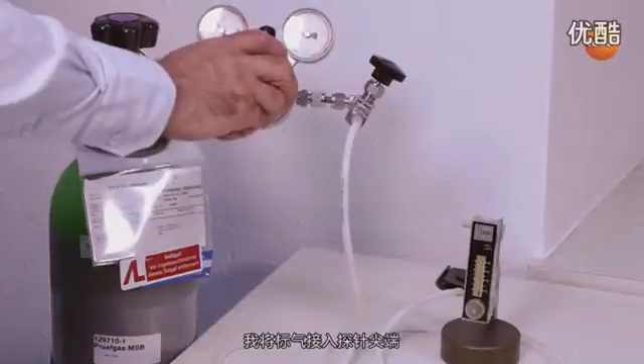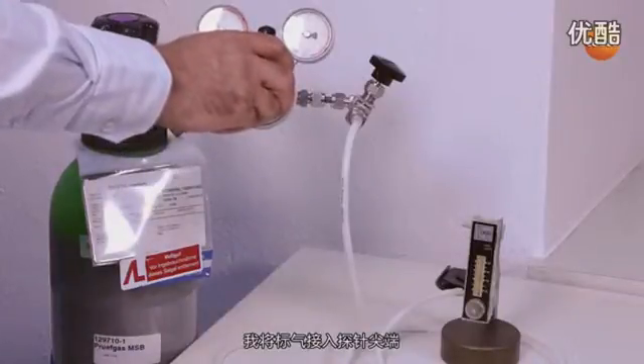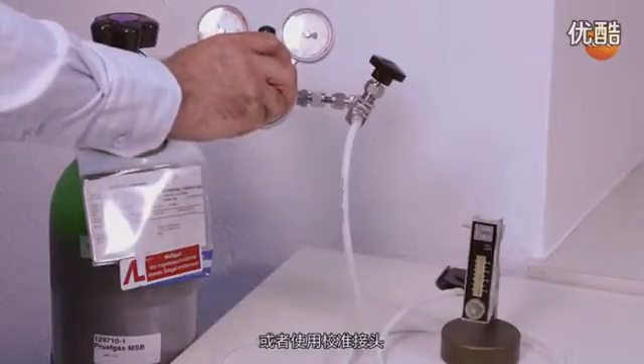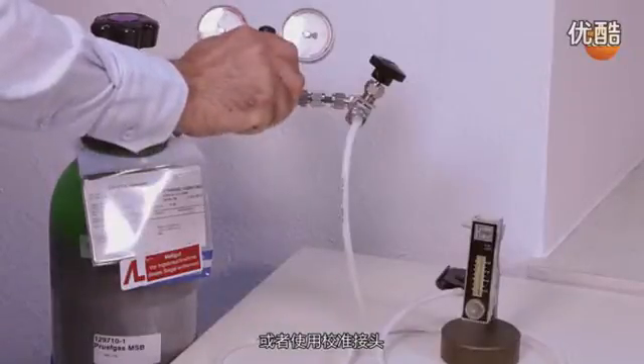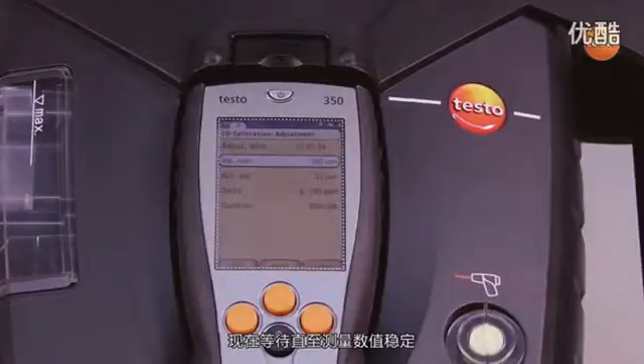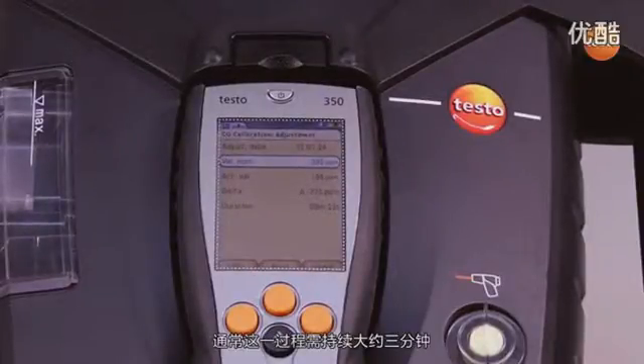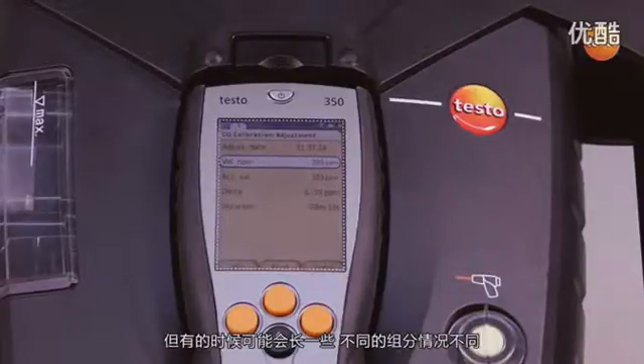I apply the calibration gas to the probe tip without pressure. Alternatively, a service adapter can be used. We now wait until the measurement value has stabilized. This is different from component to component. As a rule, it takes around 3 minutes, but it can take longer.